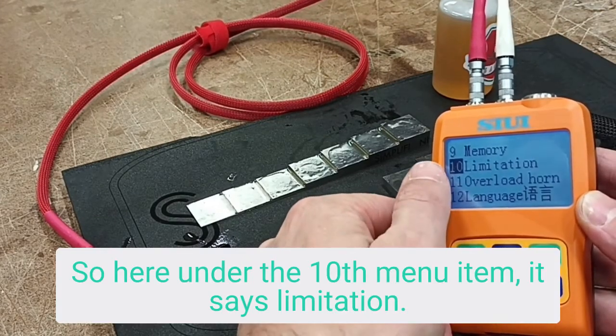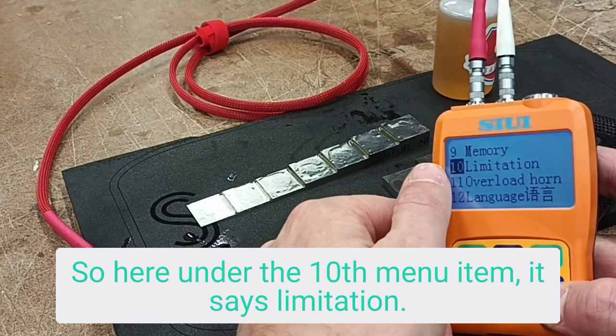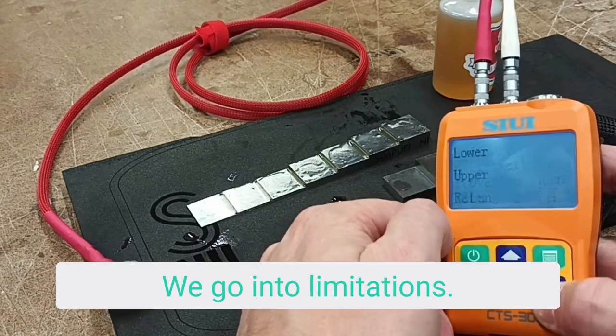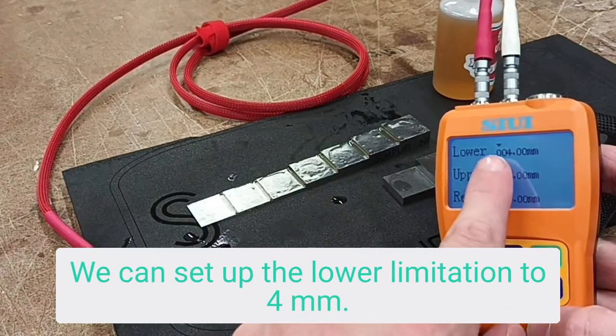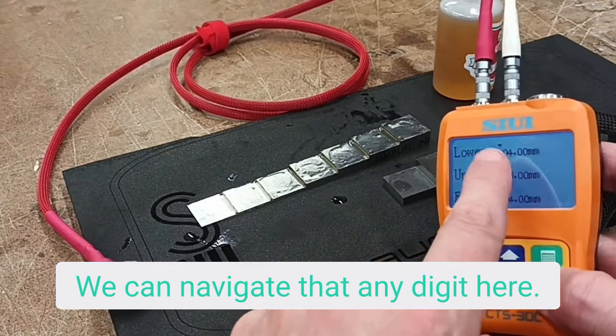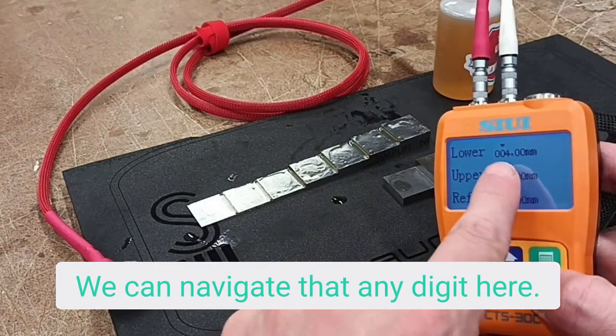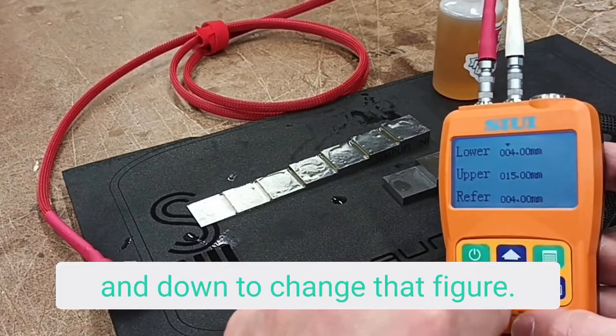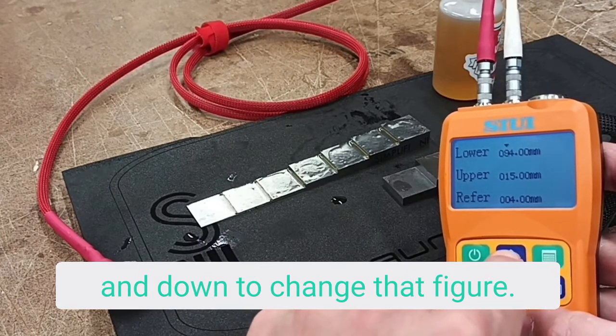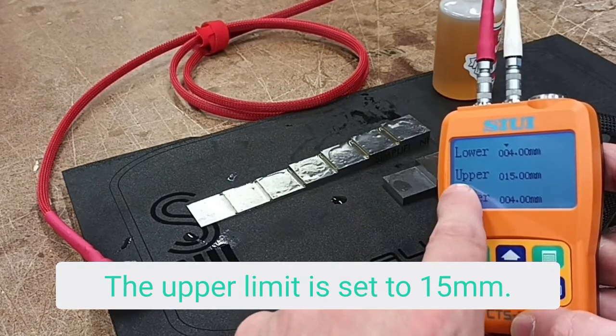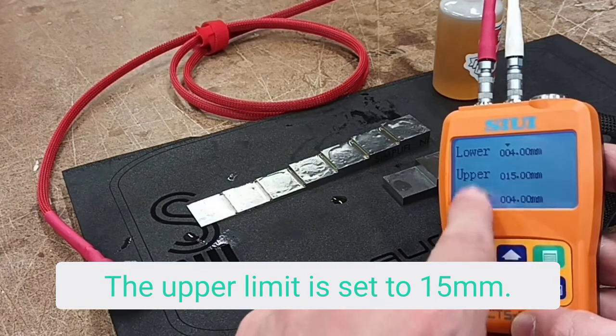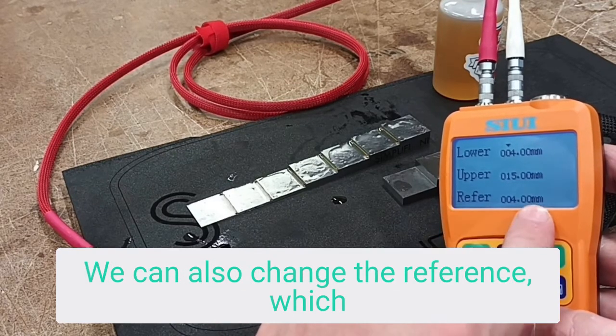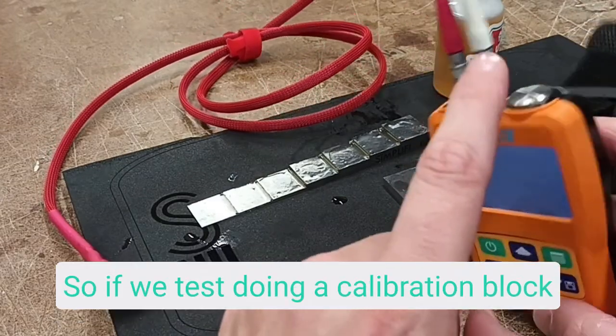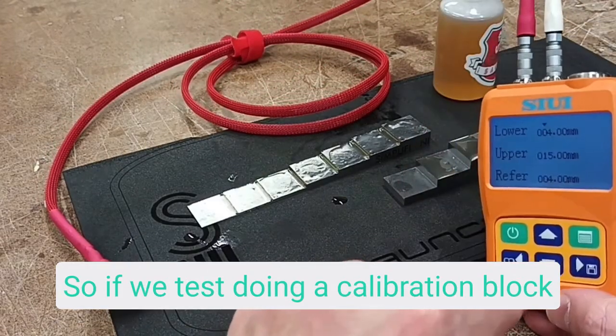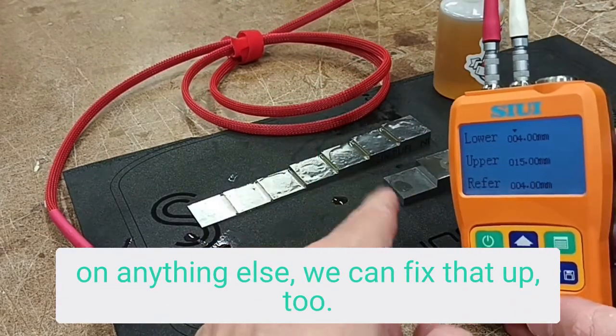So here under the 10th menu item, it says limitation. We go into limitations. We can set up the lower limitation to 4mm. We can navigate that, any digit here, and then we can scroll up and down to change that figure. The upper limit is set to 15mm, and we can also change the reference, which is this 4mm test block inside. So if we're doing a calibration block on anything else, we can fix that up too.